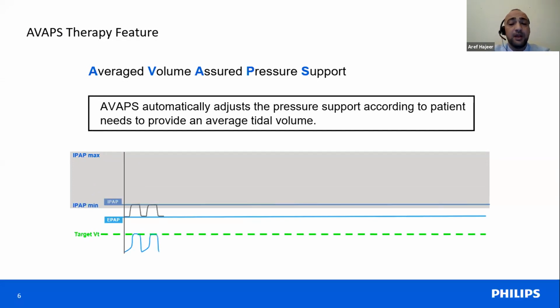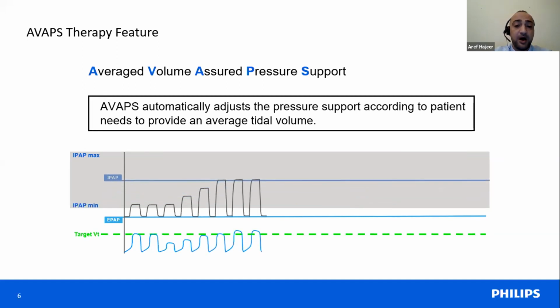The device will start on the minimal pressure all the time. So if the tidal volume of the patient is achieved, as we can see here in the graph, on the green line, it has achieved the target tidal volume. So the device is giving minimal pressure as it continues to achieve the target tidal volume. Once something happens to the patient and the tidal volume drops down, if you don't have the automatic Avaps, you need to increase the pressure for the patient manually. But with this feature, the device will automatically start to increase the IPAP to compensate the tidal volume and make it fixed or near to the target value.